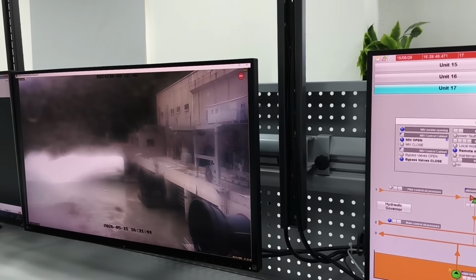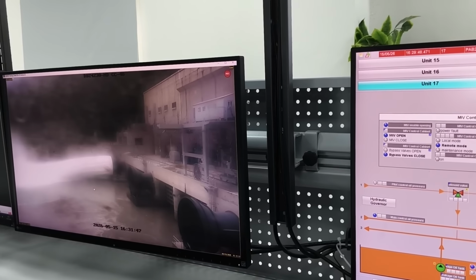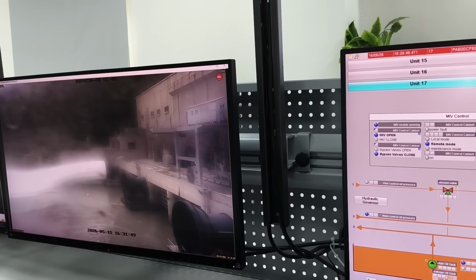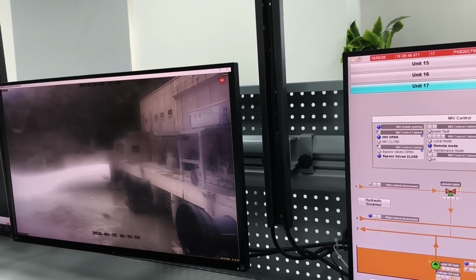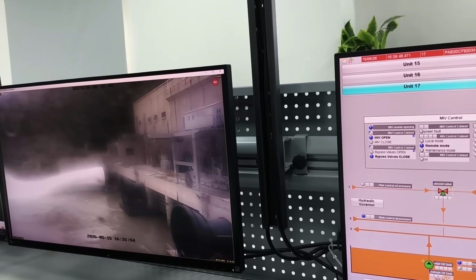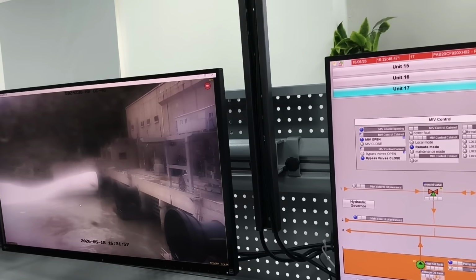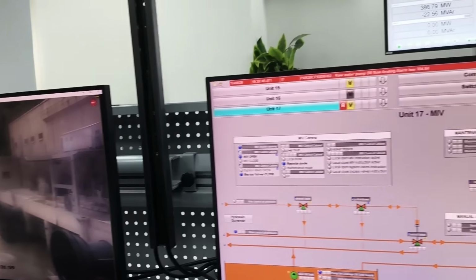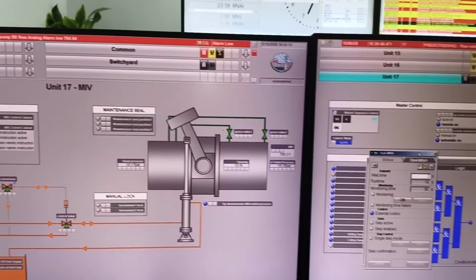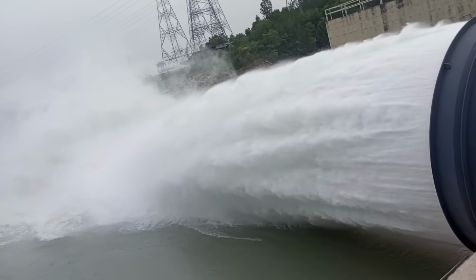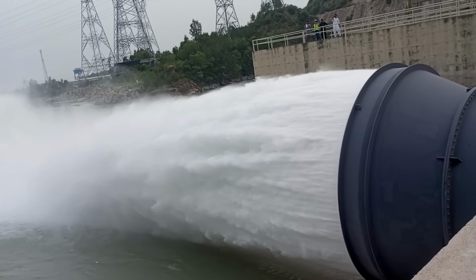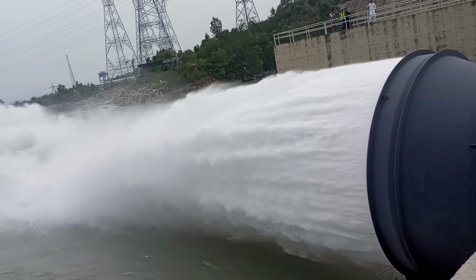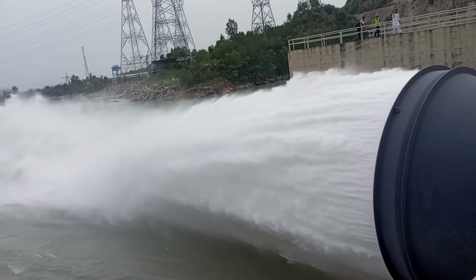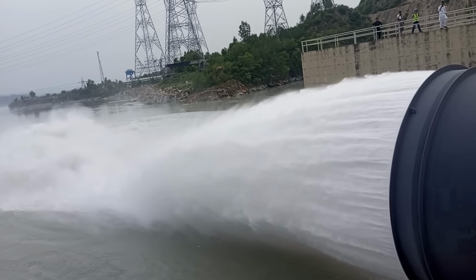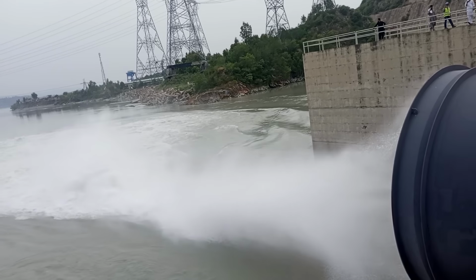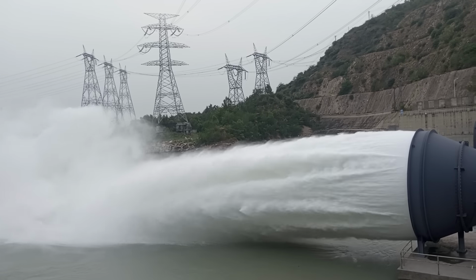if a sudden load rejection occurs later during the operation, these valves must open immediately to release dangerous pressure surges before they become destructive. This powerhouse has no surge shaft, which means these PRV systems are the primary defense against hydraulic transients and water hammer effects. If the valve fails this test even once, the startup sequence stops instantly. The unit goes nowhere, no exception. With the safety valves verified, the machine is now officially authorized to move. But before water can strike the runner blade, the physical locking system must be removed.